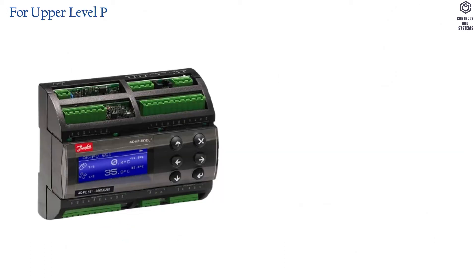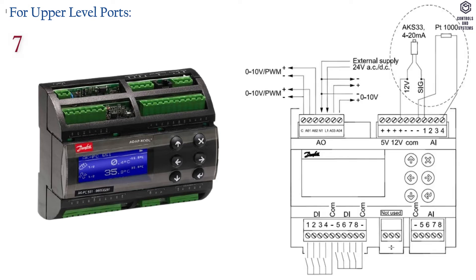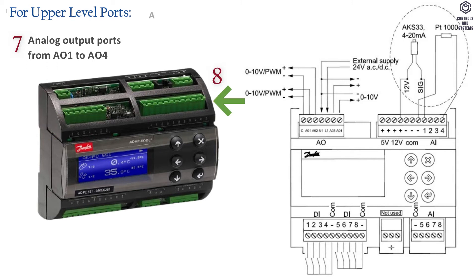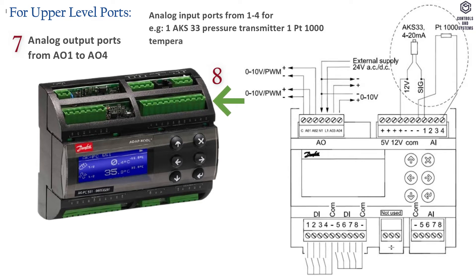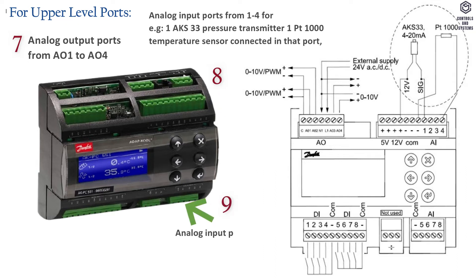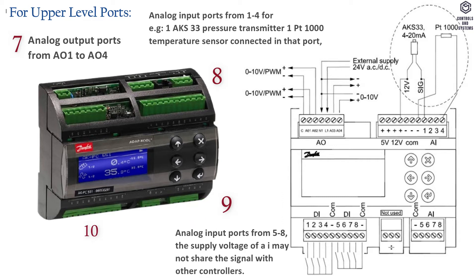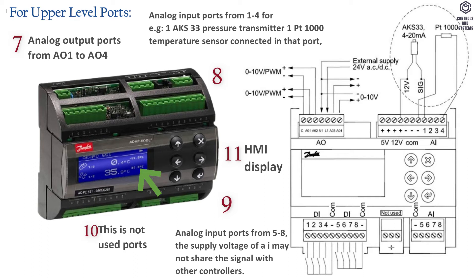For the 4 upper level ports: port 7 is the analog output ports AO1 to AO4. Port 8 is the analog input ports 1 to 4 — for example, an AKS 33 pressure transmitter or a PT1000 temperature sensor connected to that port. Port 9 is analog input ports 5 to 8. Port 10 is unused ports. Port 11 is the HMI display.